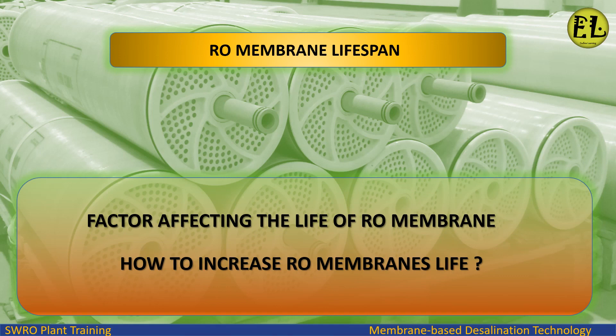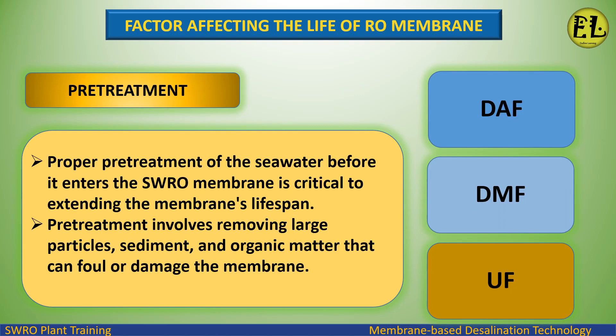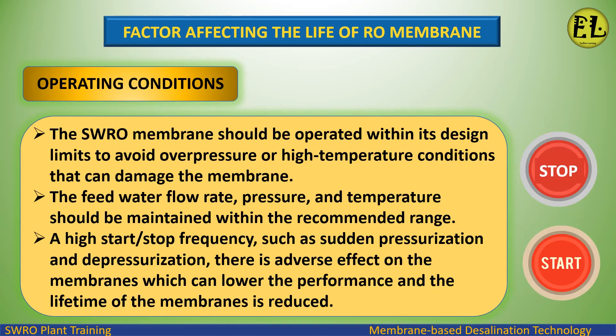Proper pretreatment of the seawater before it enters the SWRO membrane is critical to extending the membrane's lifespan. Pretreatment involves removing large particles, sediment, and organic matter that can foul or damage the membrane. Common pretreatment types include dual media filtration, dissolved air flotation (DAF), and ultrafiltration (UF).